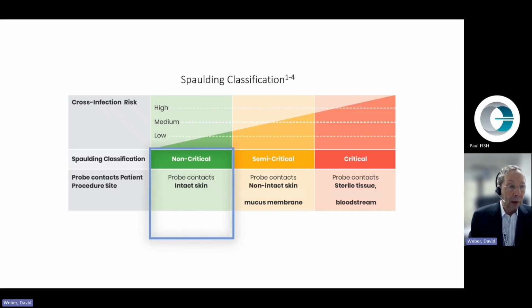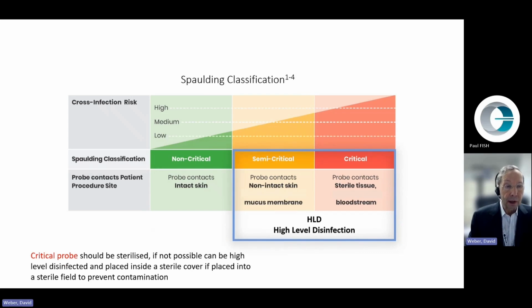We have non-critical under the Spaulding classification. This would be that the device, including a probe, contacts only intact skin, and the risk of cross-transmission is low. Then we have semi-critical. A probe contacts non-intact skin or a mucous membrane, and the risk of cross-infection is considered medium. Finally, we have critical. A probe contacts sterile tissue or the bloodstream, and the risk of cross-infection is high. Now, for semi-critical and critical items, we would either use sterilization, or if the device cannot be sterilized, we would use high-level disinfection.